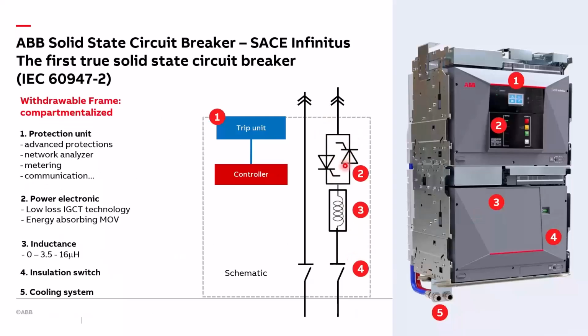So two IGCTs in anti-parallel, then we have a metal oxide varistor in parallel, an inductance in series in order to limit the current and to guarantee the breaking capacity, and a DC disconnector in series in order to guarantee the galvanic isolation in open position, because you know the semiconductors are not able to guarantee the galvanic isolation, since there are no fixed and mobile contacts like in a traditional disconnector.